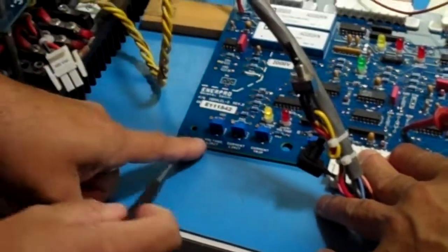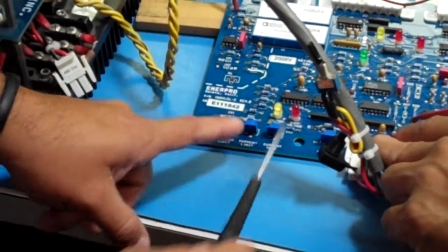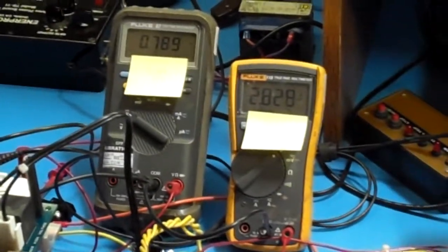Now keep in mind, because it's such a low voltage limit command, I'm voltage regulating. I'm just going to bring that up a little. Right there. And I'm going to try to current regulate with the current limit. Again, shouldn't be any trip because the feedback, which is going to be less now, is less than 1 volt. It's still below the current trip threshold.